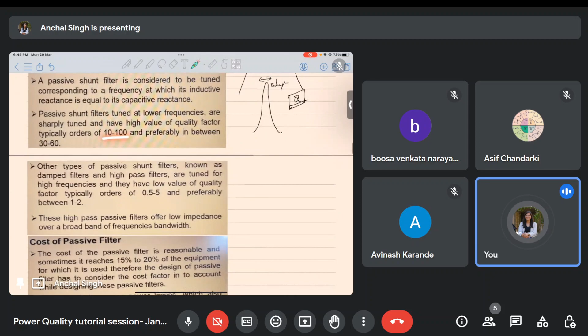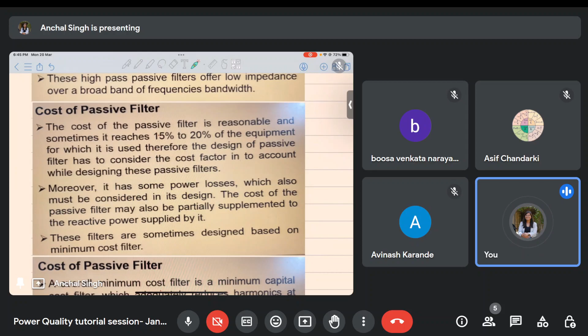The reason why passive filters are very popular is that if in an application the cost of the filter is in the range of 15 to 20% of the total cost of the system, then they are very efficient, and people will definitely go for them. In case the cost reaches around 50%, then people might not use them. So you have to do the cost analysis based on the rating of your passive filter. Only then do you go for passive filters.